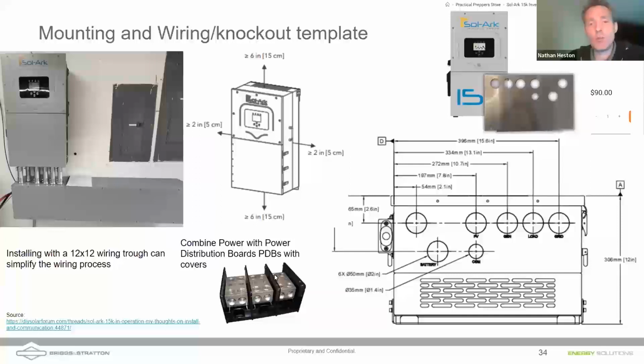On spacing, you need 6 inches above and below the inverter, and that's for the fans to be able to run the cooling through the back. The inverter needs 2 inches on either side unless you're paralleling units, and then you actually need 6 inches between inverter units per Sol-Ark's spec.